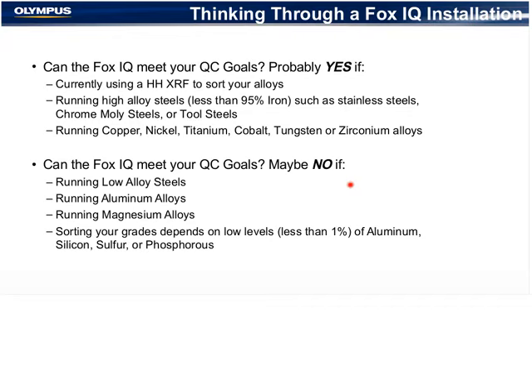The Fox IQ might not be able to meet your application needs if you're running low alloy steels. We have customers that are running low alloy steels, but we need to look at your list and think through your analytical goals, because it's harder to separate low alloy steels, and the ability to measure carbon is not something that X-ray is able to do. Running aluminum alloys, we have customers that are using the system for aluminum alloys, but again, we can't do everything that might want to be done with an aluminum alloy, so that would be something we'd have to look at closely. And magnesium alloys are similar. Sorting your grades depends on low levels, less than 1% of aluminum, silicon, sulfur, or phosphorus. We would want to look carefully at that application. We might not be able to do it.